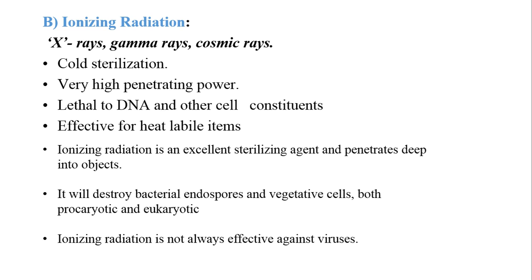Ionizing radiations have high penetration power, which is why they can achieve sterilization. Examples include X-rays, gamma rays, and cosmic rays, though gamma rays are primarily used for sterilization. Sterilization through ionizing radiation is called cold sterilization because it does not increase temperature. Ionizing radiation is lethal to DNA and other cell constituents and is effective for heat-sensitive items.